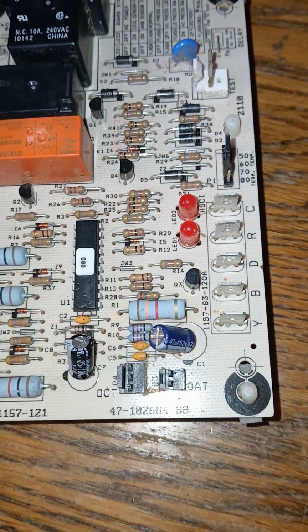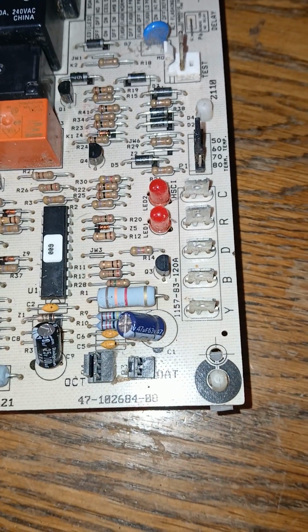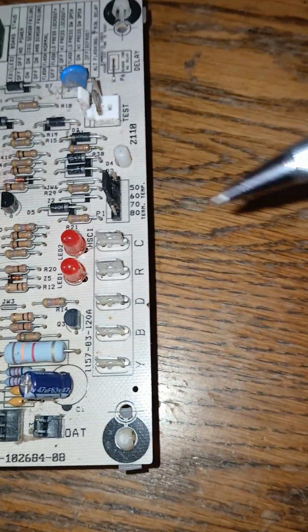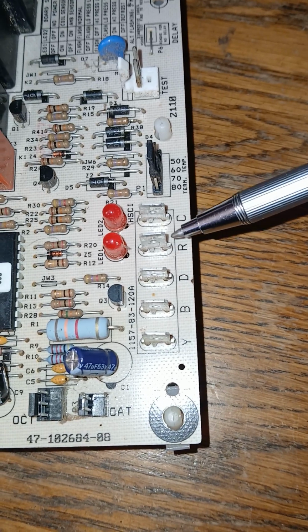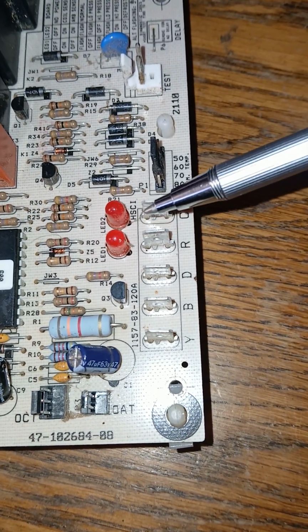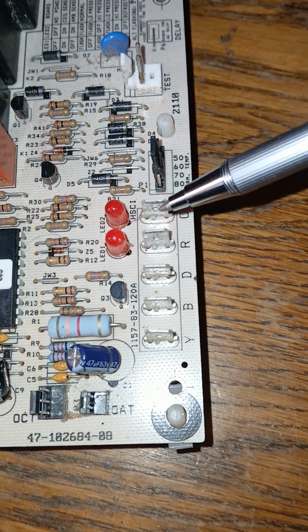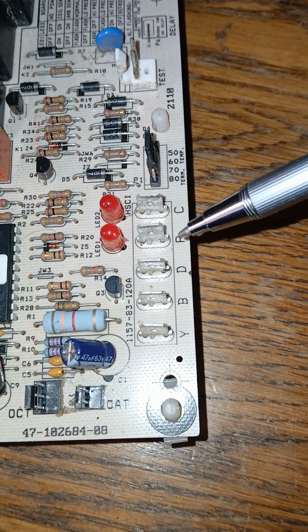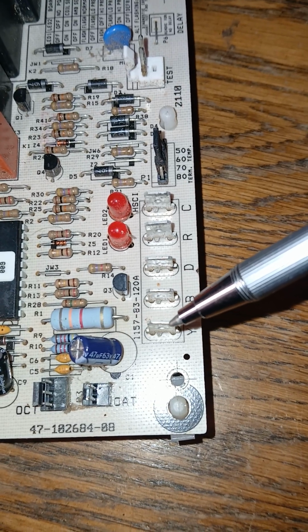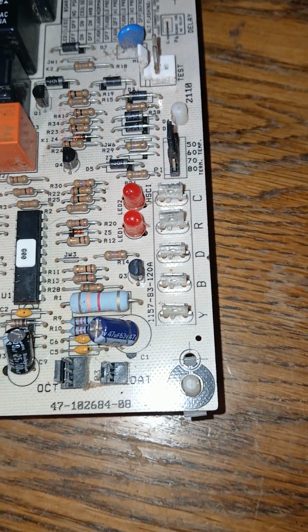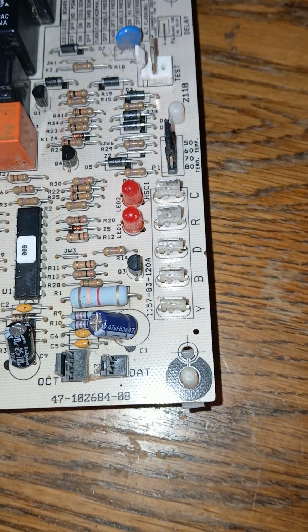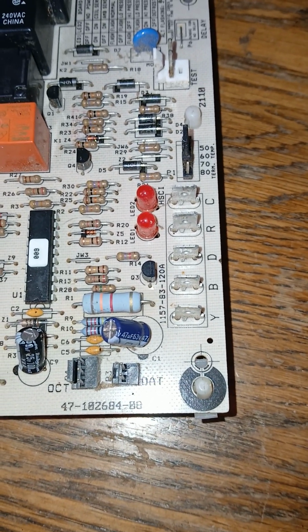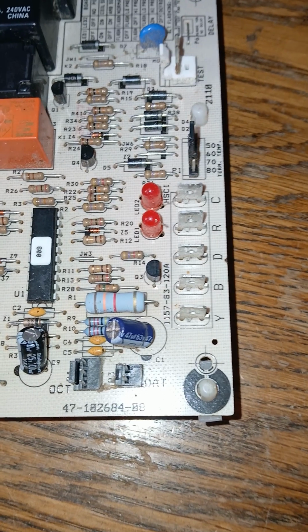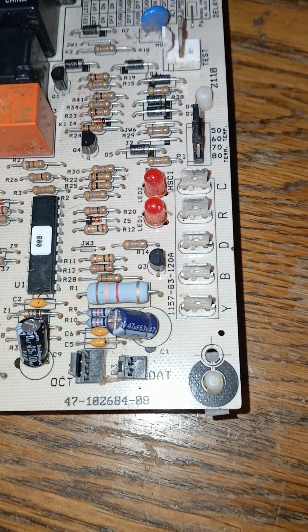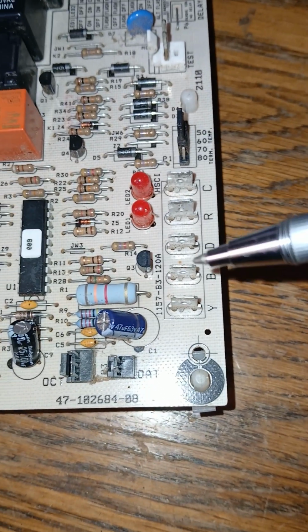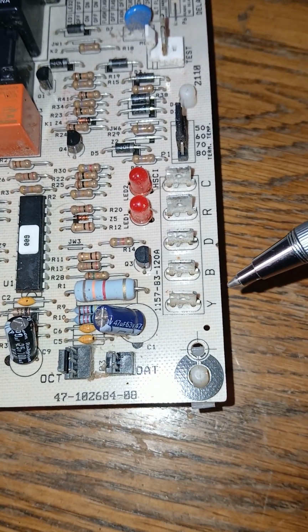But we've been identifying particular parts here. So earlier we had identified the red and the C. Red incoming 24, the C makes the loop, the blue wire normally. Then we have the Y wire. The Y wire perhaps should energize the cooling, or it could be used perhaps for the heat too. I'm not certain on that. The HVAC gurus can elaborate on that in the comment section.